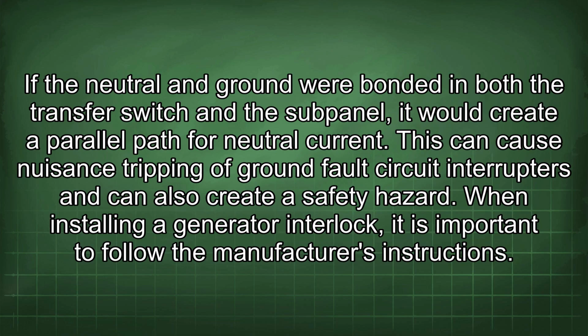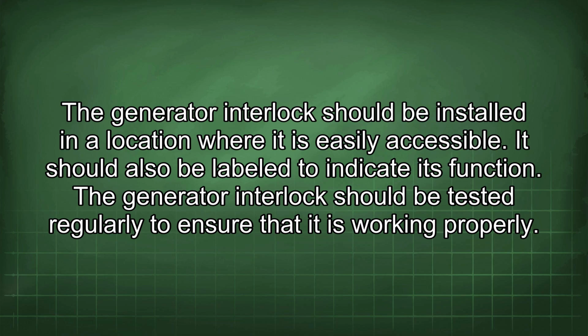If the neutral and ground were bonded in both the transfer switch and the subpanel, it would create a parallel path for neutral current. This can cause nuisance tripping of ground fault circuit interrupters and can also create a safety hazard. When installing a generator interlock, it is important to follow the manufacturer's instructions. The generator interlock should be installed in a location where it is easily accessible. It should also be labeled to indicate its function. The generator interlock should be tested regularly to ensure that it is working properly.